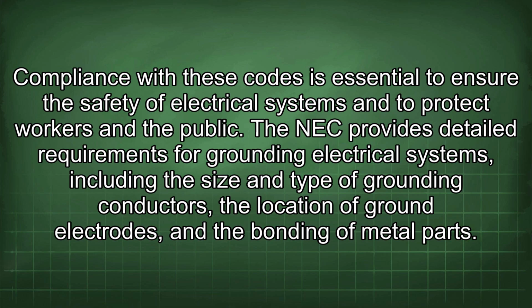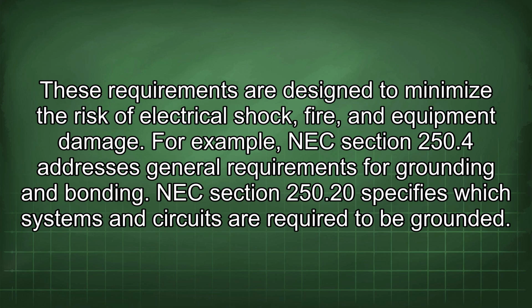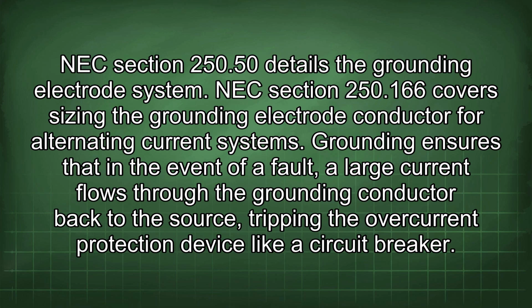The NEC provides detailed requirements for grounding electrical systems, including the size and type of grounding conductors, the location of ground electrodes, and the bonding of metal parts. These requirements are designed to minimize the risk of electrical shock, fire, and equipment damage. For example, NEC Section 250.4 addresses general requirements for grounding and bonding. NEC Section 250.20 specifies which systems and circuits are required to be grounded. NEC Section 250.50 details the grounding electrode system.